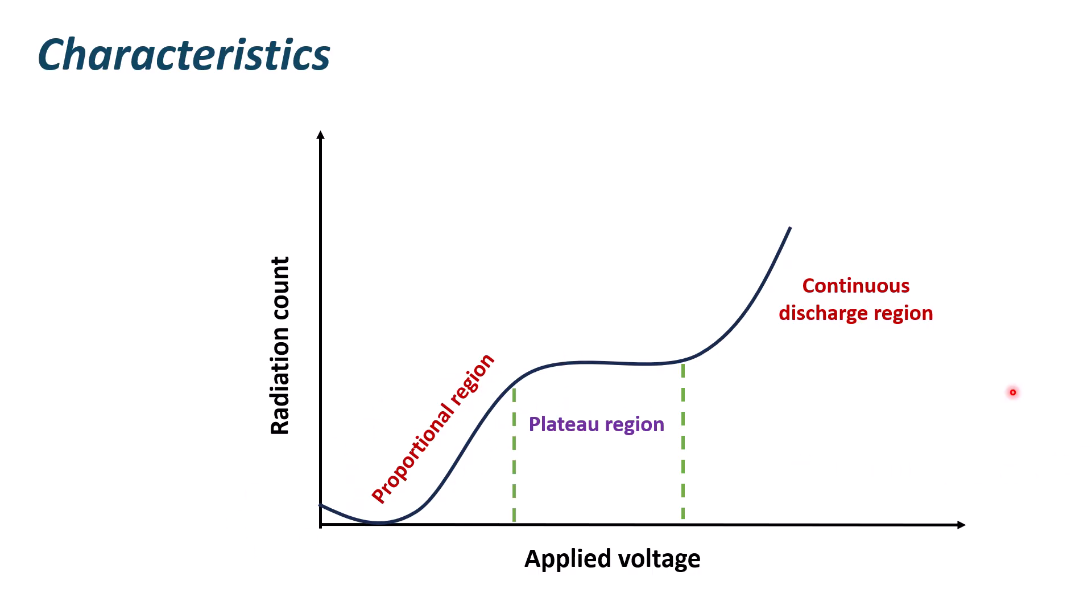Then, there will come a moment where the count rate stays constant over a specific area if the applied voltage is raised higher. This region is termed as Geiger or plateau region. The Geiger-Müller operation takes place in this region only.